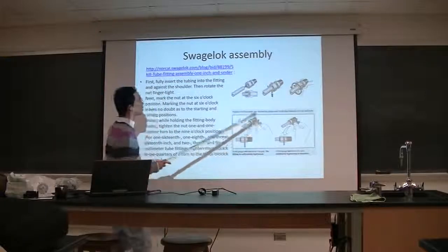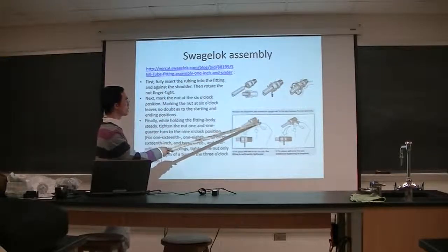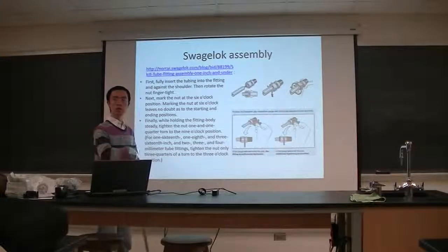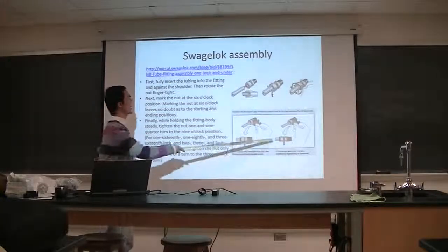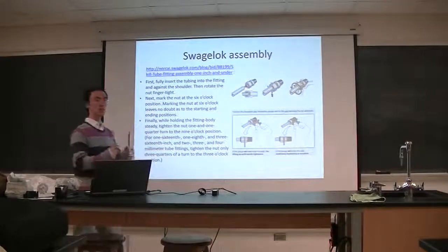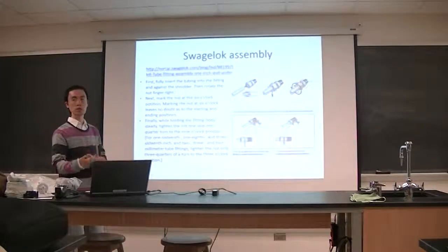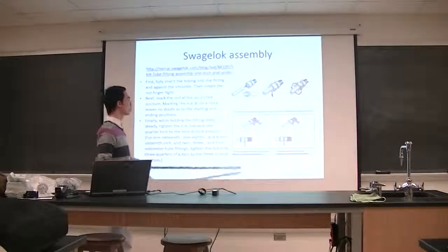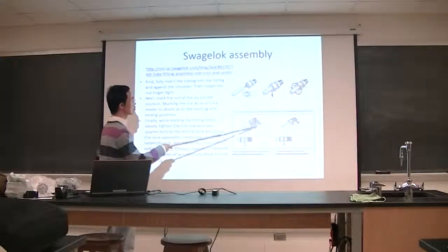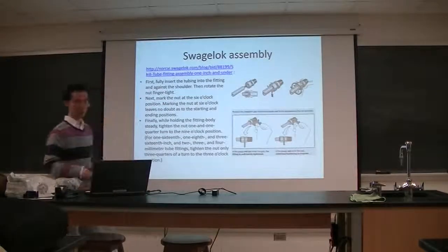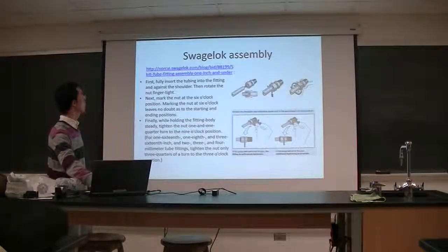And then after you tighten it, you should use a spacer to check the space between the two nuts. If you tighten too much, next time you can hardly open it, or even if you open it, you cannot use it again. So there is a dedicated space checker for you to check the space between the nuts.